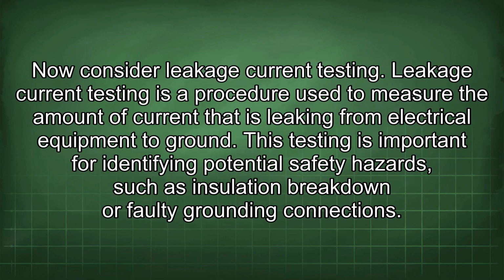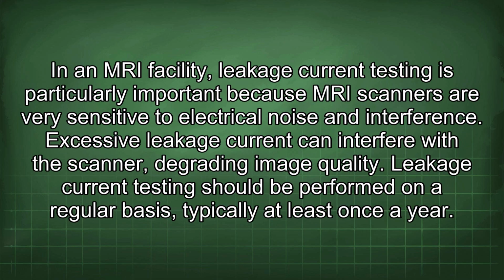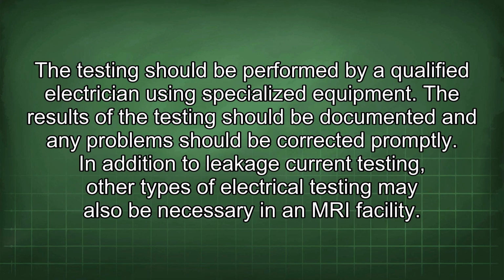Now consider leakage current testing. Leakage current testing is a procedure used to measure the amount of current that is leaking from electrical equipment to ground. This testing is important for identifying potential safety hazards such as insulation breakdown or faulty grounding connections. In an MRI facility, leakage current testing is particularly important because MRI scanners are very sensitive to electrical noise and interference. Excessive leakage current can interfere with the scanner, degrading image quality. Leakage current testing should be performed on a regular basis, typically at least once a year. The testing should be performed by a qualified electrician using specialized equipment.